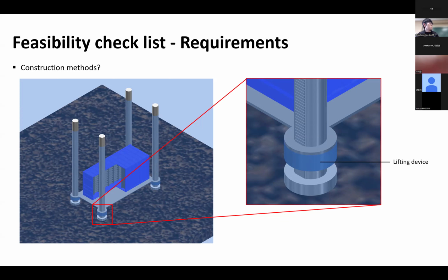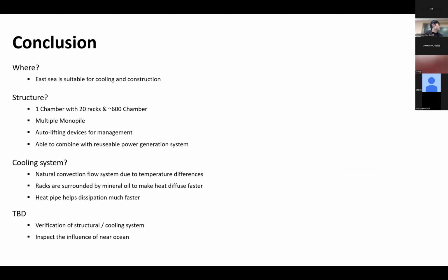This is the conclusion for the midterm presentation. For location selection, the East Sea is more suitable than the Yellow Sea. For the structure, one container or chamber can handle about 20 racks, and we'll need about 500 or 600 chambers, with a multiple monopile structure and auto-lifting device management. For the cooling system, a natural convection flow due to temperature differences can be used, and racks are surrounded by mineral oil so they can diffuse heat faster.